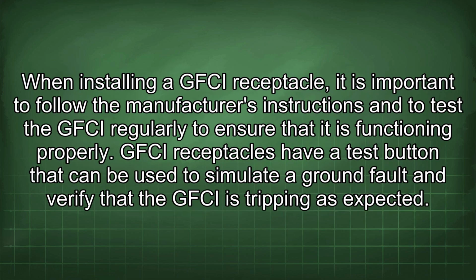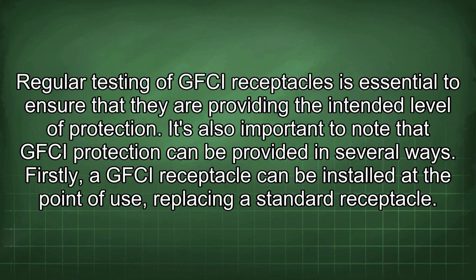When installing a GFCI receptacle, it is important to follow the manufacturer's instructions and to test the GFCI regularly to ensure that it is functioning properly. GFCI receptacles have a test button that can be used to simulate a ground fault and verify that the GFCI is tripping as expected. Regular testing of GFCI receptacles is essential to ensure that they are providing the intended level of protection. It's also important to note that GFCI protection can be provided in several ways.